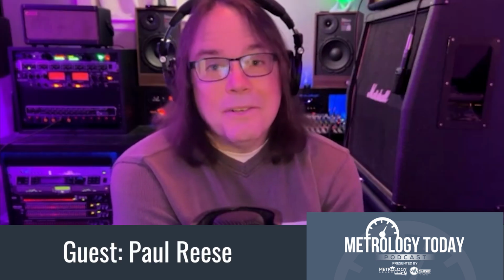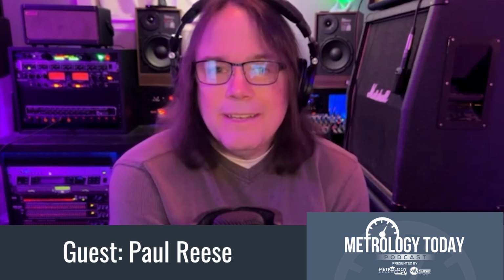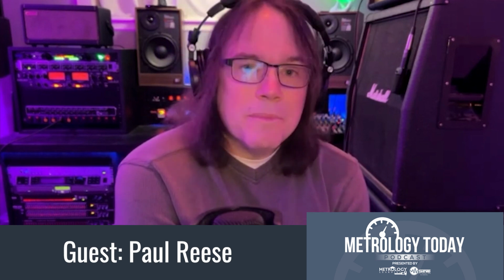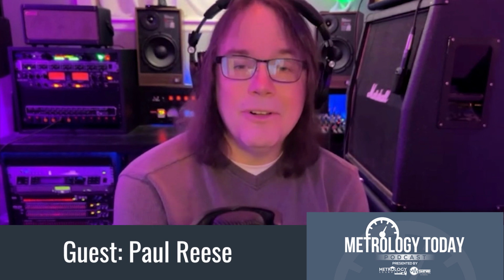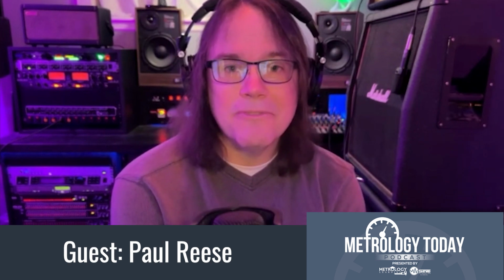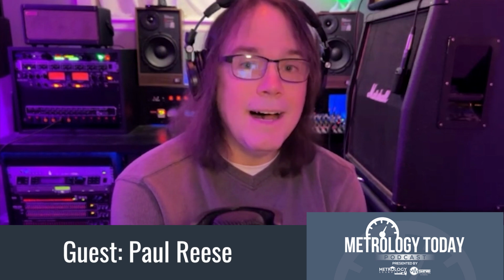And Paul, I think you can elaborate a little bit on those, because we've talked numerous times about this. Yeah. So I think what you're getting at is guard banding. What do you consider something in tolerance? Does it have to be in tolerance by an amount equivalent to the uncertainty of the measurement process, which is certainly what you'd do if you're going to limit the false accept risk, but you are going to drive false reject risk up high if that's your guard band.